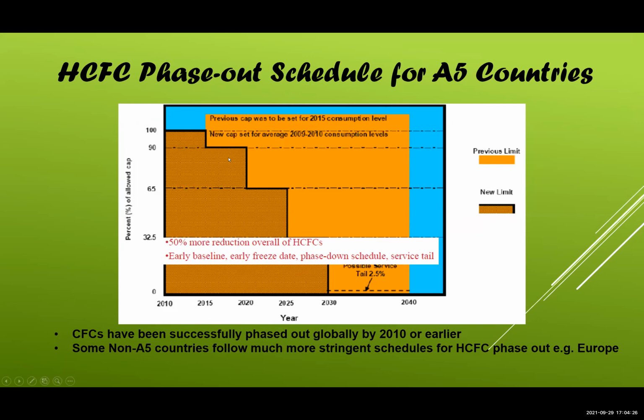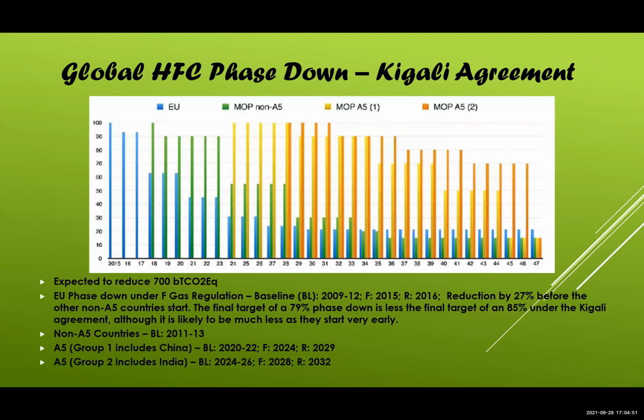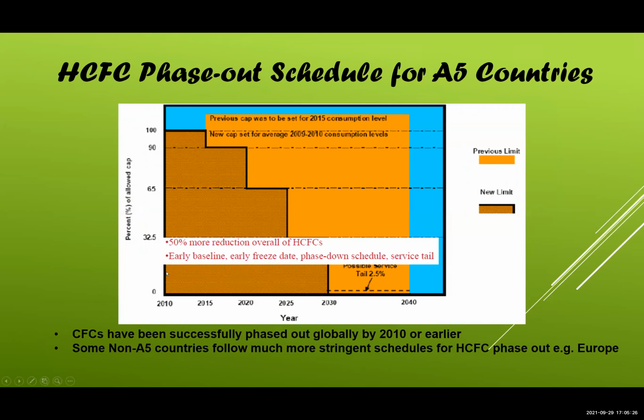Although the Montreal Protocol gives you a lot of leverage, the global trend is faster than this, and therefore most countries, in order to be in the market, phase out all old refrigerants and start introducing new refrigerants. Now, developing countries are handling HCFC phase out, and I want to differentiate between HFC phase down and HCFC phase out. CFCs and HCFCs were phased out, meaning by 2040, all HCFC consumption should become zero. Like if you see my previous slide, it should become zero.